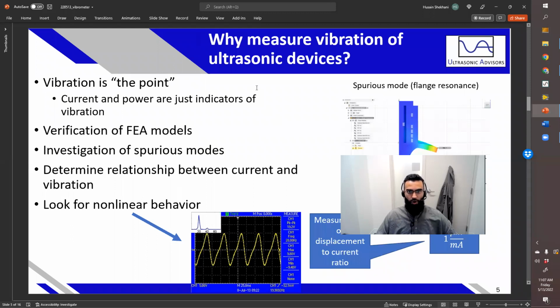So firstly, why measure the vibration, which I'm talking about as the displacement or the velocity of your ultrasonic devices? Why is that important? Well, vibration, or mechanical oscillation, is actually the point. It's not simply just to power your device with a certain frequency. You're looking to make an impact, you're looking to make a particular physical function in the real world, and that happens through the electromechanical conversion of piezoelectricity from voltage then to force or displacement, however you would like to phrase that.